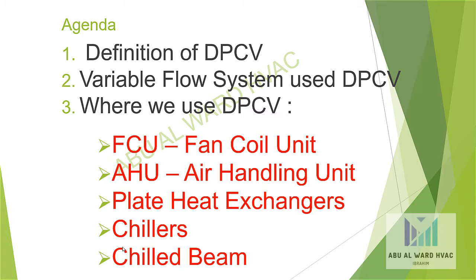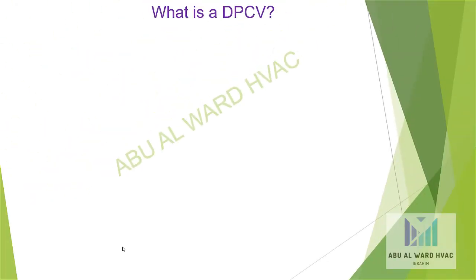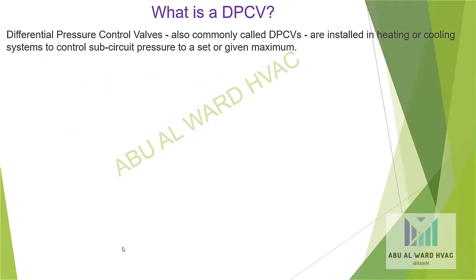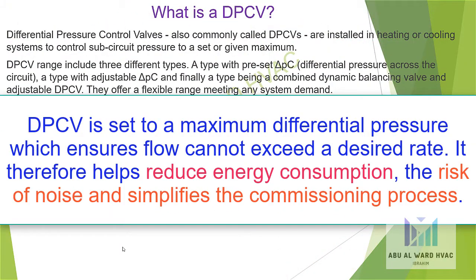What is a DPCV? Differential pressure control valves, commonly called DPCVs, are installed in heating or cooling systems to control sub-circuit pressure to a set or given maximum. DPCVs include three different types: a type with preset Delta PC, a type with adjustable Delta PC, and a type being a combined dynamic balancing valve and adjustable DPCV. They offer a flexible range meeting any system demand.